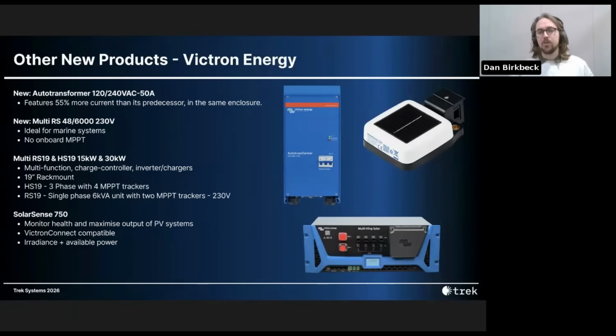Victron's also introduced the Multi-RS 19 and HS 19. These are 19-inch rack-mount inverter charger combinations with integrated solar charge controllers, making installation much quicker and cleaner. The Multi-RS 19 is a 48-volt single-phase 6 kVA unit with dual MPPT trackers built in, while the HS19 is a 3-phase model with 4 MPPT trackers, and both are currently 230 volt only.